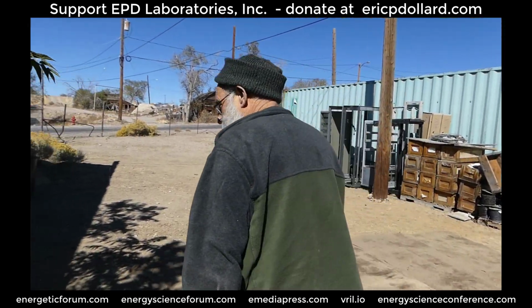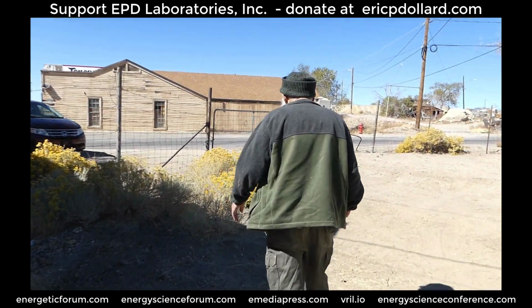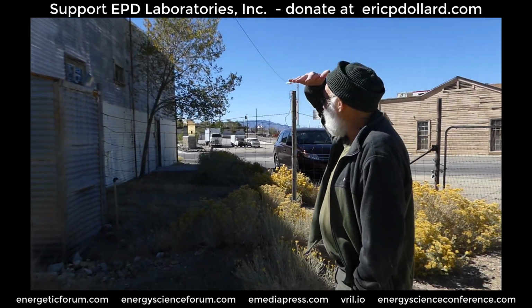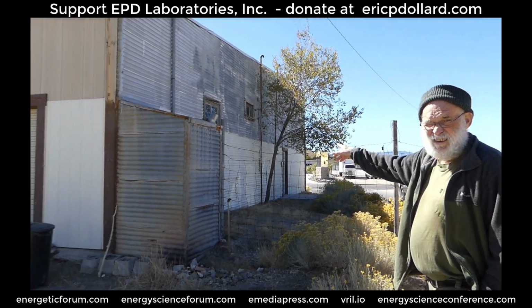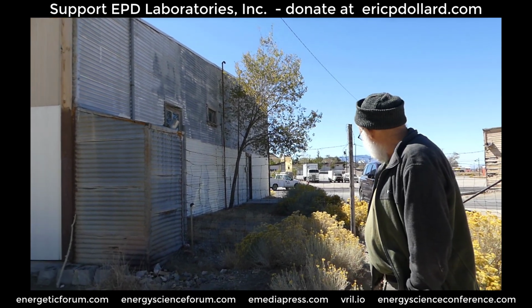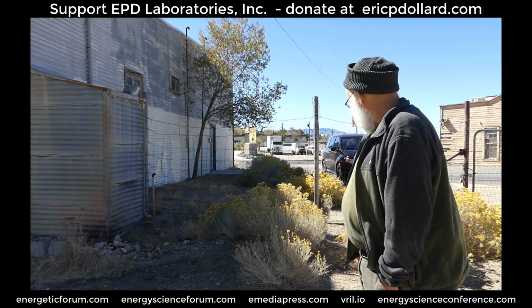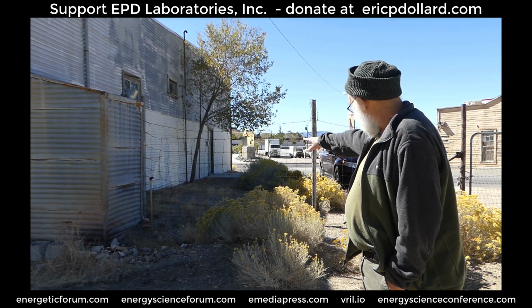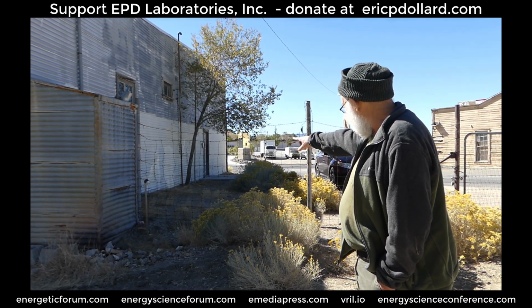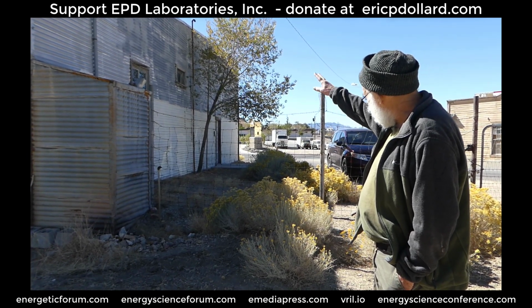So the big problem with the electrical system right off is, of course, because this is an MV energy, the high voltage neutral is connected to the low voltage neutral, which is then connected to the ground rod and the metal pipes. And so the entire side of the building is now hot with the high voltage neutral, which is not acceptable in any kind of research situation, and it's just downright dangerous. So it places a strong potential difference possibility against the water tanks. The water tanks are right next to it, and their vents are right next to it, and they're at zero potential, and then right next to that is this metal building that can be any kind of potential depending upon lightning strikes or ground faults to the system or harmonics or any of that. And so right off it's a shock hazard.